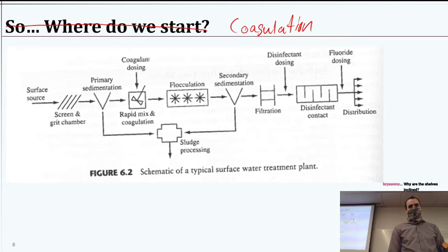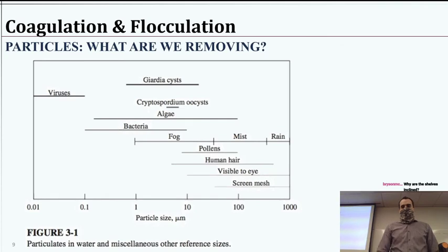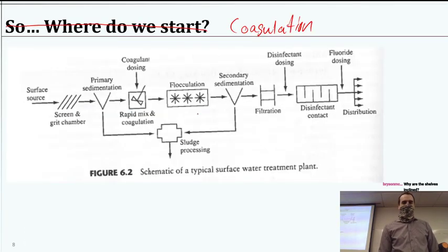So really what I'm going to talk about now is coagulants, how and why they work, particle stability, how we can manipulate it, and in general, the coagulant dosing. We'll cover this a little when we talk about the flocculation mixing, but it's really a small reactor, a CSTR, very small with a very high flow rate, rapidly mixing and moving right along. So we don't do a lot of modeling of that reactor in particular. It just goes in, mixes, we inject a bunch of the chemicals and make sure it's well mixed before it goes into the flocculation chambers. Ultimately the goal is to have a second sedimentation after we make larger particles, use gravity again, and see what else we can remove.